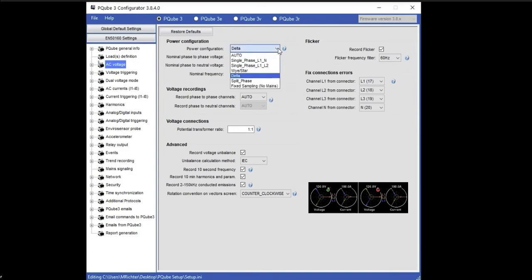If we have a Y circuit, these are now enabled. So we can turn these, leave them auto or on, or perhaps you did not want to know the phase to neutral channels in your Y configuration and you can turn them off. This just shows the flexibility of what is recorded at the PQube. Going back to delta. The PQube can be connected directly to a high voltage circuit. 480 volts is just fine.